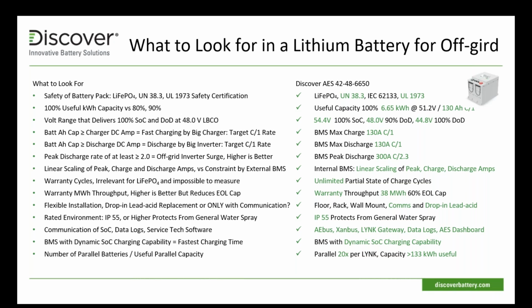So it can be complicated to get peak capacity and a large charge and discharge out of systems if you're involved in something above about 10 kilowatts of product. Ours has an internal BMS system, so we don't really face this challenge. We linearly scale our peak charge and discharge amps, so it's pretty simple.